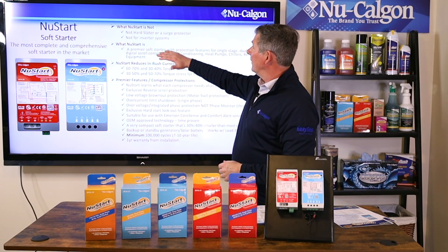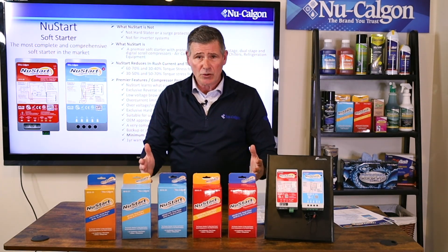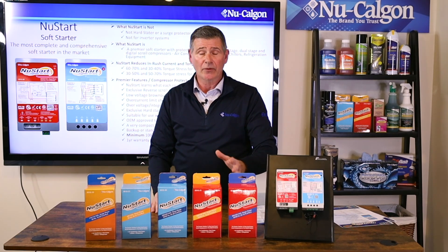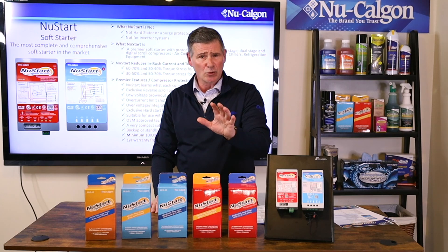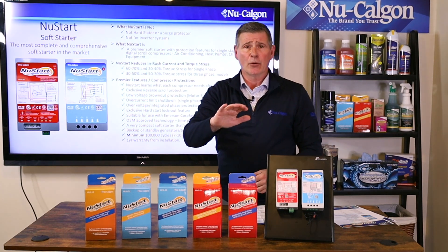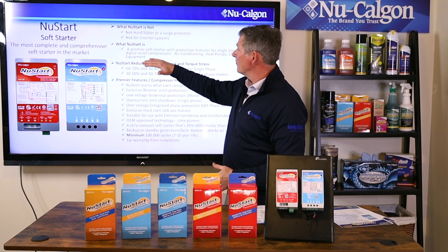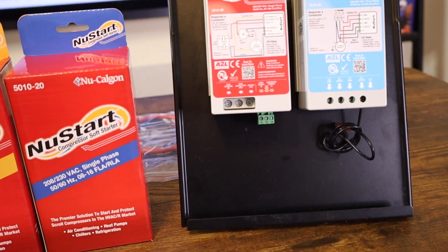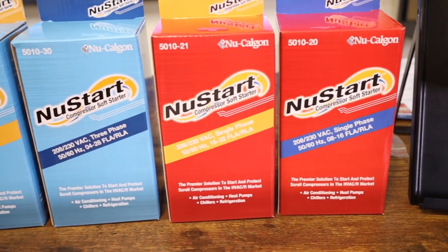It's completely the opposite. These are not surge protection devices — there are plenty of surge protection devices out there, but these do not provide any surge protection whatsoever. These are just soft starters with some incredible features and benefits. They are also not for inverter systems. NuStart soft starters are a premier soft starter with protection features for single stage, dual stage, and digital scroll compressors for air conditioning systems, heat pumps, chillers, and refrigeration equipment.